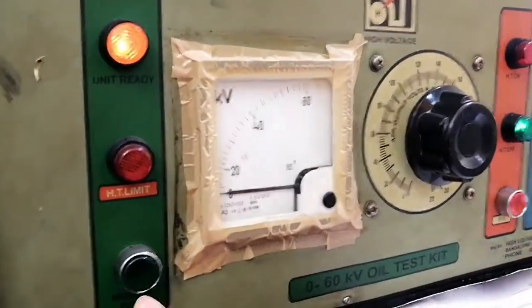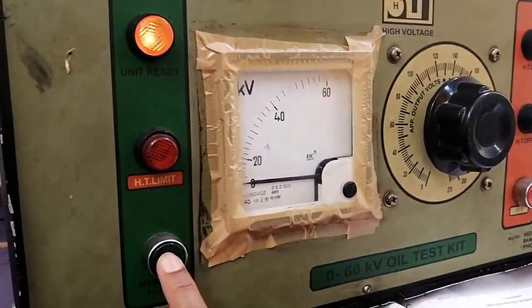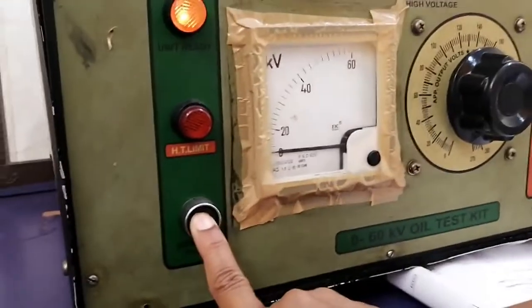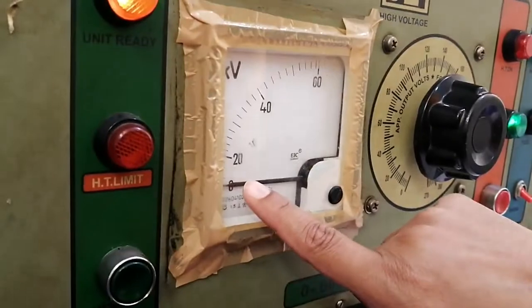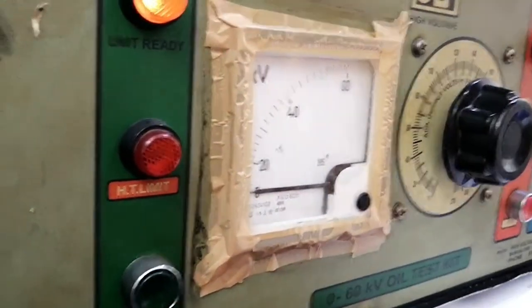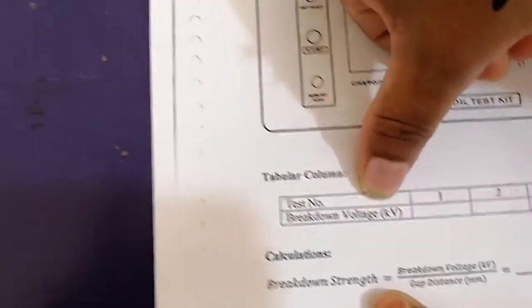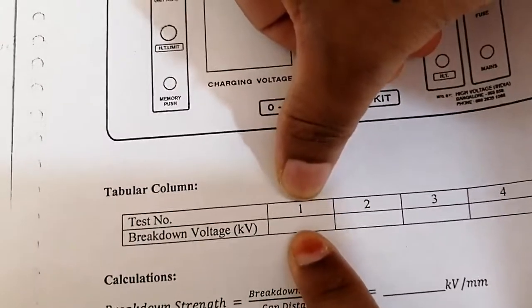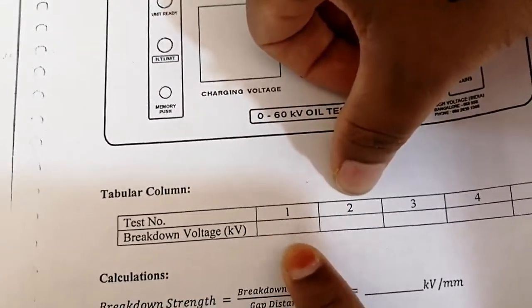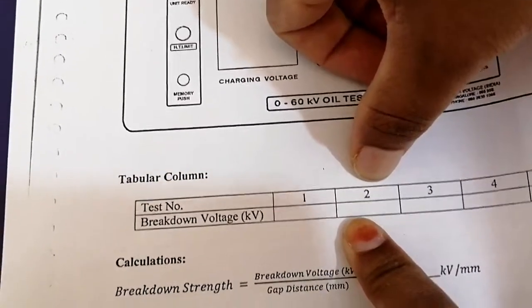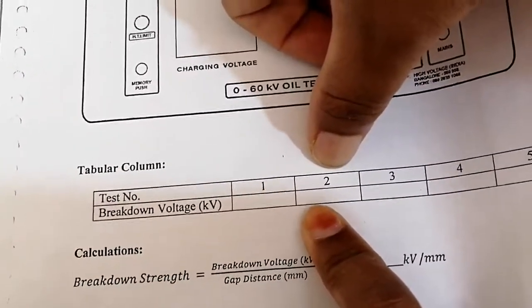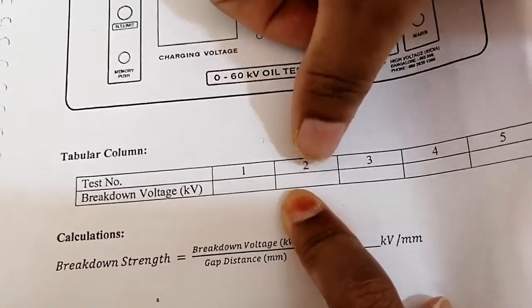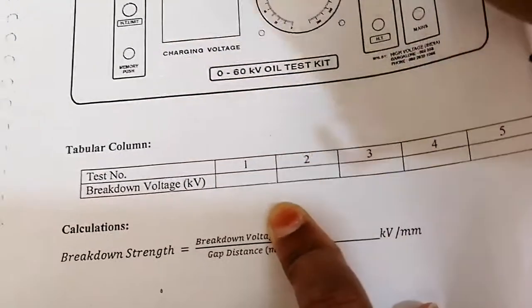In order to read that value, there is a memory push button. Once you press this button, the voltmeter will show at what voltage the oil broke down. You have to record that value in the tabular column. In the first trial, so much voltage is the breakdown. Then the second trial you have to do after a 15 minute gap, so that the transformer oil comes down to normal temperature. Then do the second reading, and again note down the breakdown voltage by pushing the memory button. In the same way, do 5 trials.